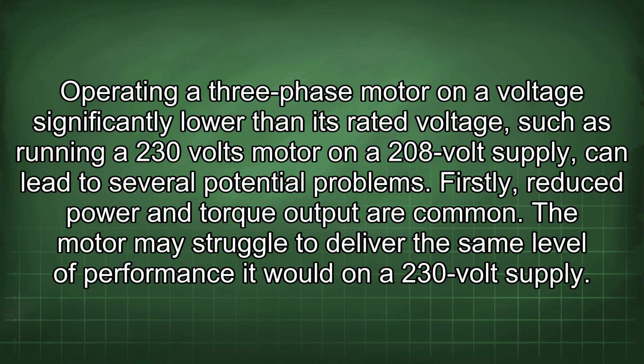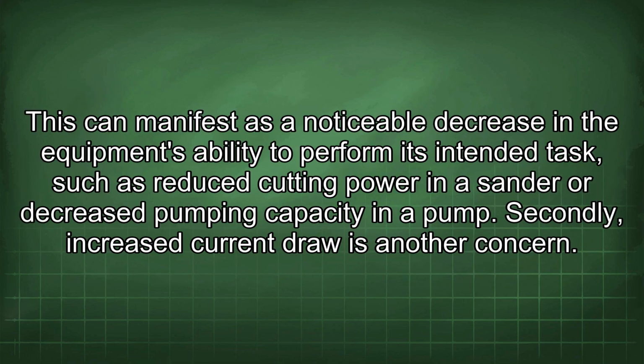Firstly, reduced power and torque output are common. The motor may struggle to deliver the same level of performance it would on a 230 volt supply. This can manifest as a noticeable decrease in the equipment's ability to perform its intended task, such as reduced cutting power in a sander or decreased pumping capacity in a pump.